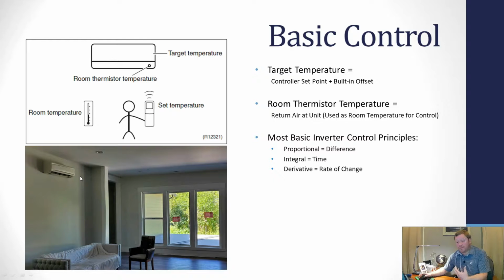What that means is, hot air, warm air rises, and if we're sensing our room temperature from the indoor unit, which is important to note, you're not sensing temperature from that handheld controller. You're sensing temperature from a return air thermistor which is located at the indoor unit. If you're sensing temperature up by the ceiling, that sensed temperature is typically going to be somewhere around 3 to 3.5 degrees warmer than where you're sitting on the couch. So keep that in mind as we go through the process of how your system is operating.